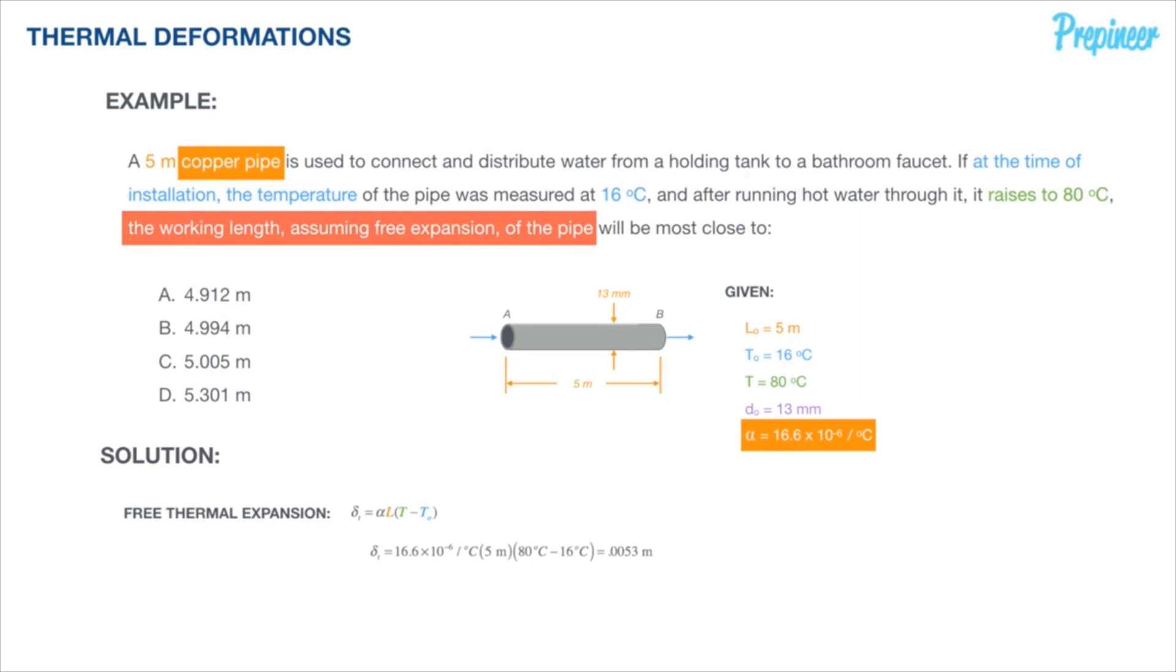That's an important piece of data we need, but we are asked to determine what the working length is. The working length is simply taking our original length and then either adding or subtracting what the delta will be based on our change in temperature. In this case, we're increasing and raising the temperature, which then gives us an expansion of our copper pipe of 0.0053. So we plug in the data to determine that our working length is going to be 5.005 meters.